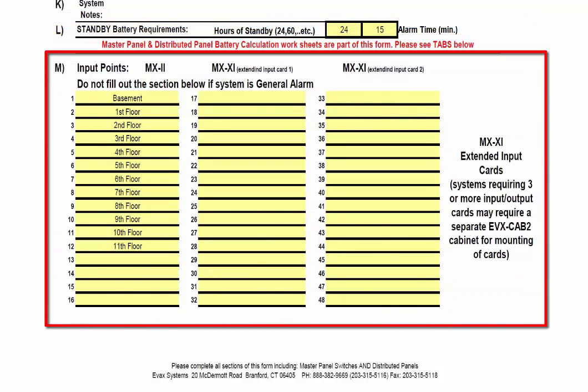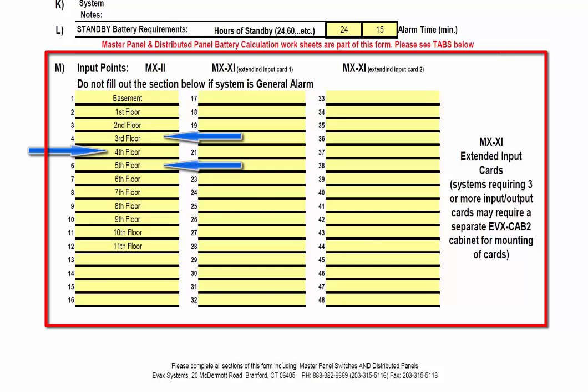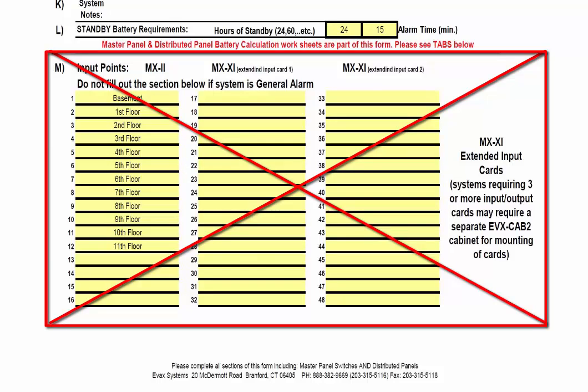Input Points is where the Fire Alarm Control Panel interfaces with the EVAX Voice Panel, telling it how to operate or what needs to be activated. You will need to list all input points that will trigger the EVAX, similar to what is shown on the screen. Remember that this is just an example and your configuration will vary. Since we chose to operate with a floor above and floor below operation, if there was an alarm on the fourth floor of this building, it would also play the evacuation message on floors 3 and 5. Note that Section M does not need to be filled out if your system is General Alarm.